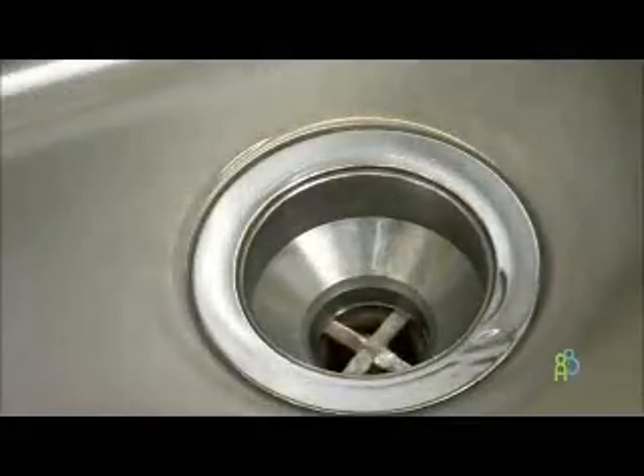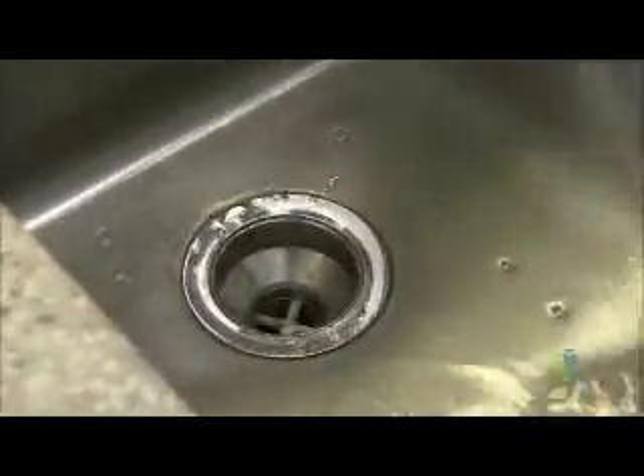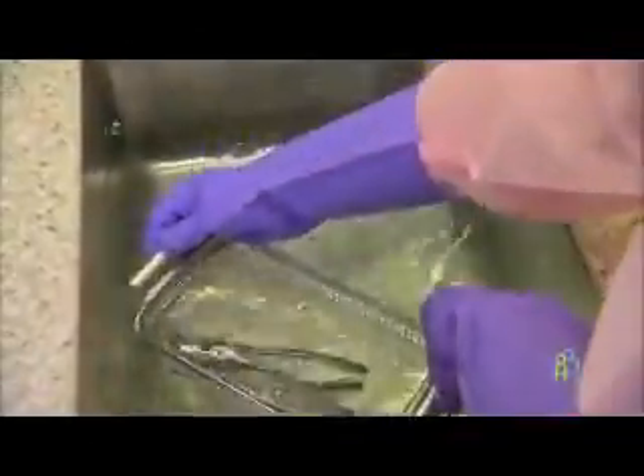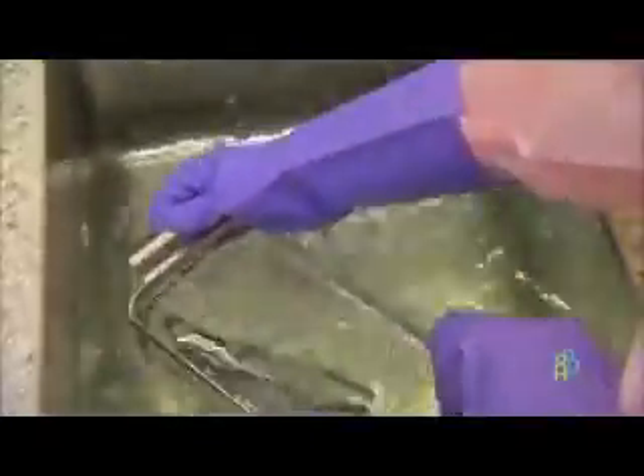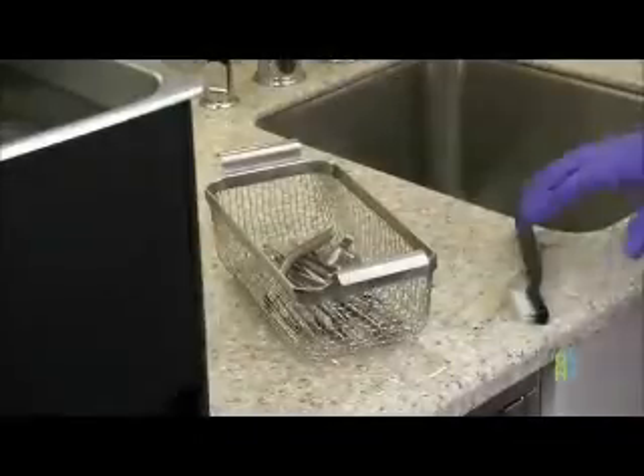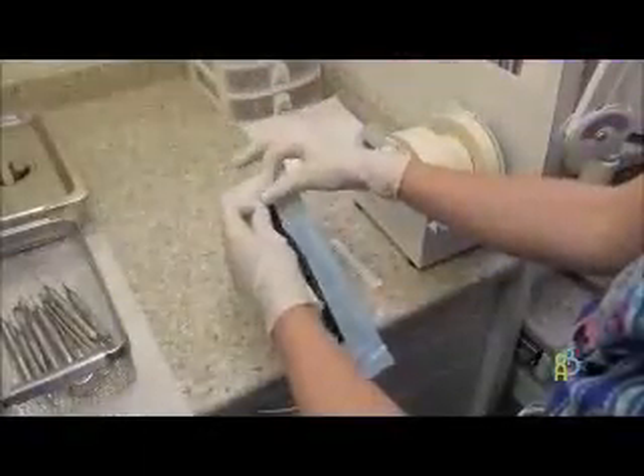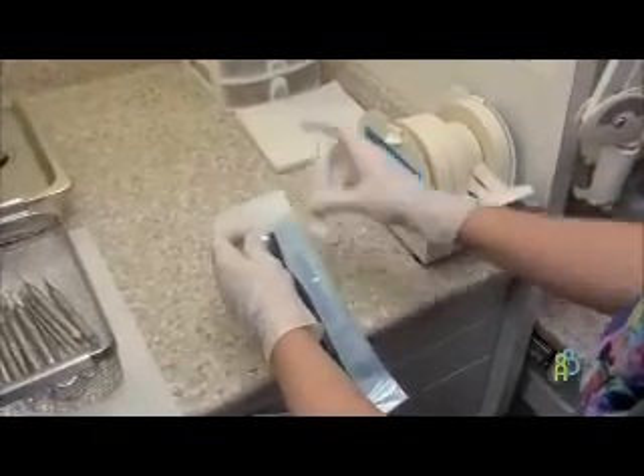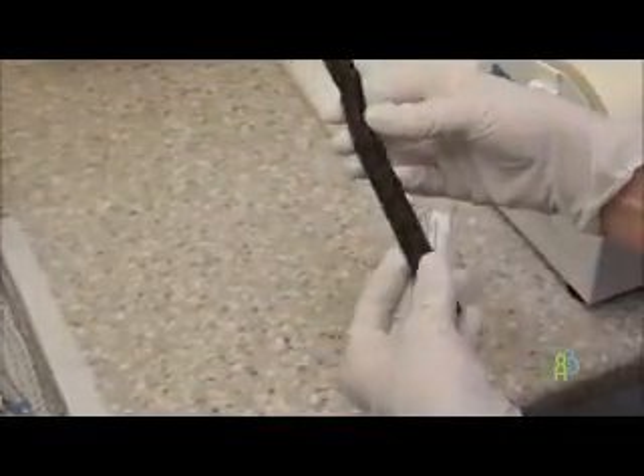If only one sink is available for cleaning instruments, drain and rinse the sink and refill with clean water. Then rinse devices below the surface of water prior to placing the devices in a clean drying area. If two sinks are available, one sink can be used for cleaning and the other can be used for rinsing instruments. Brushes and other tools used for manual cleaning must be single-use disposable or cleaned and sterilized after each use. Reusable brushes must be regularly inspected and discarded when damaged or worn. Cleaning accessories must be stored in a location that allows them to remain clean and dry when not in use.